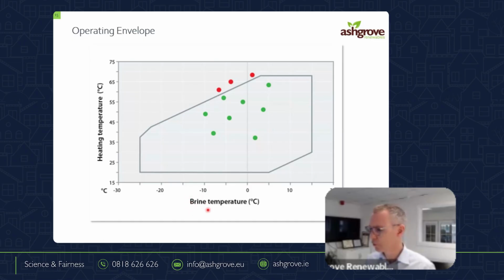For any of you who don't know, the brine is the water mixture. To stop the water from freezing on the cold side, we add antifreeze. In some places, they add a salt kind of mixture that prevents it from freezing. There is a downside, not that it matters to this graph, but when you add antifreeze to it, it reduces the amount of energy that it can transport. It decreases the specific heat capacity, therefore your pipe has to get bigger, etc. But you can see here, this is the operating envelope of this gas. It doesn't matter what it is, whatever gas it is, they'll have some sort of an operating envelope.